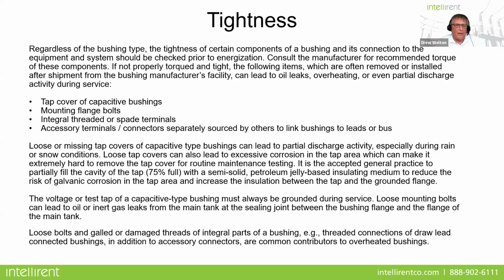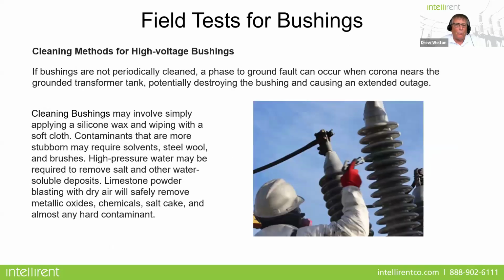Check for tightness again on your contacts on the top of the bushing. Look at the tap covers. I've taken tap covers off to do testing and found them filled with oil. Make sure that the gasket around the tap cover is solid and has a good seal, and that you tighten that down correctly. So tightness is an important thing.